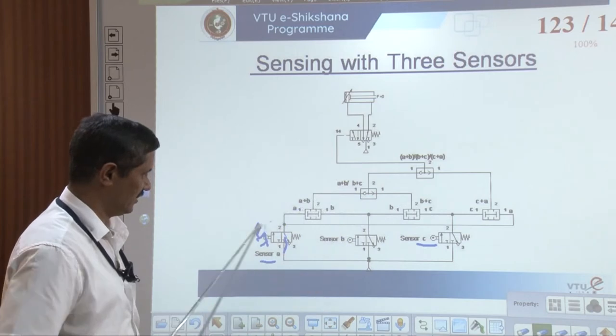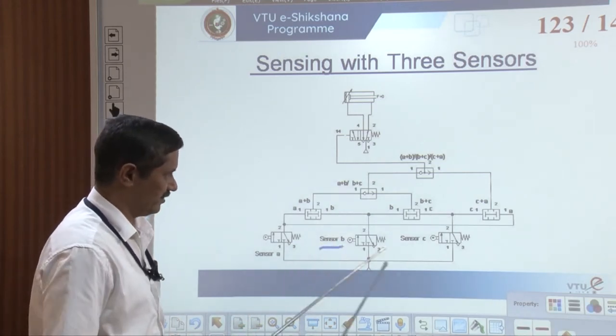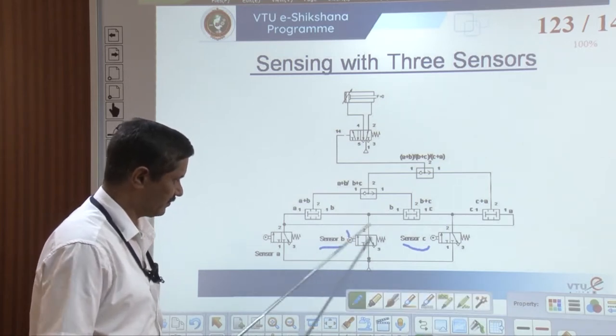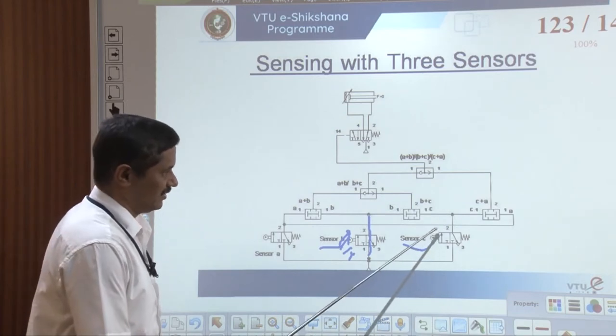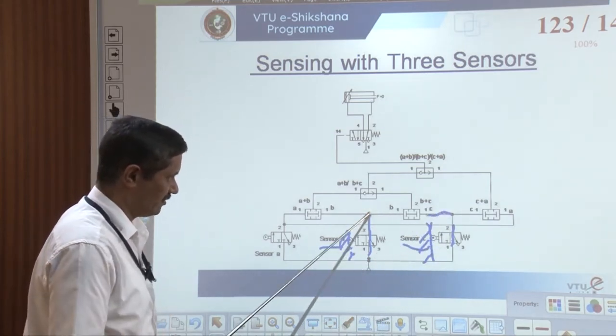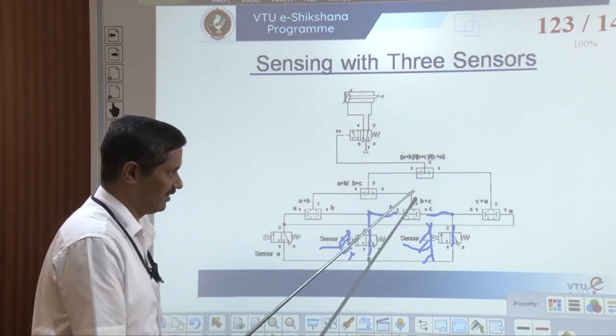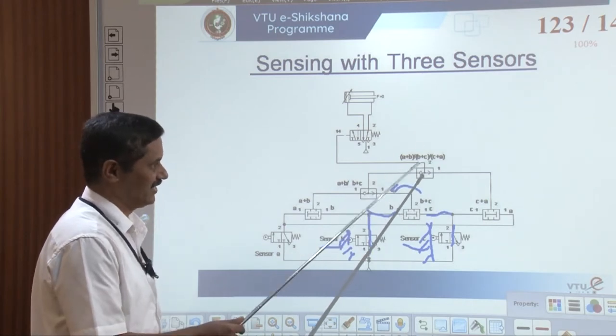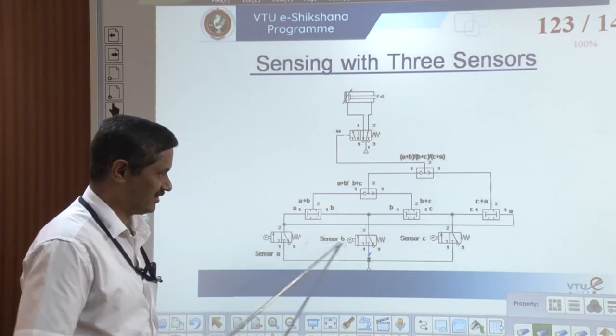The other condition is B plus C. B is pressed — one gets connected to two here; C is pressed — one gets connected to two here. Both signals come through an OR valve and move forward — there will be a signal to this OR valve. When the OR valve gets any input, it gives an output — ultimately going to the next stage through another OR valve. This is the second combination. The third set of combination is C plus A — first sensor and last sensor.